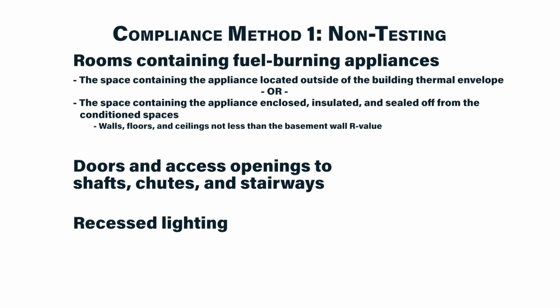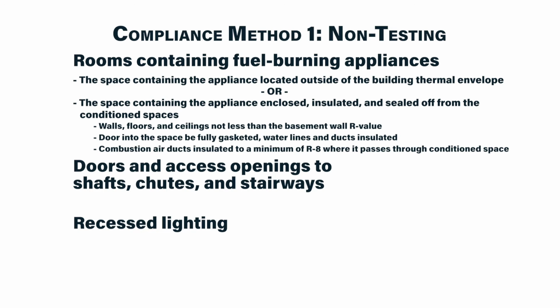The space should be sealed off from the rest of the conditioned space, and the door into the space should be fully gasketed, and any water lines and ducts in the room should be insulated. The combustion air ducts should be insulated to a minimum of R8 where they pass through conditioned space.